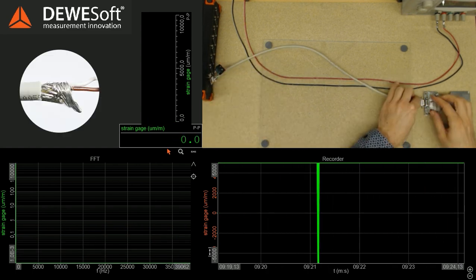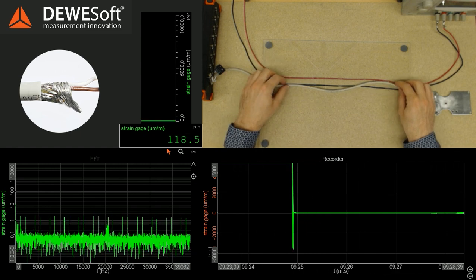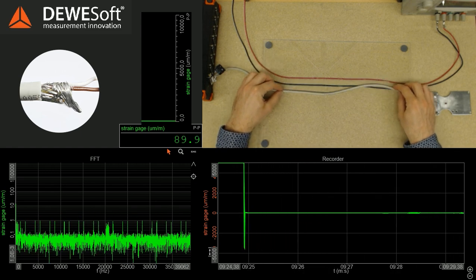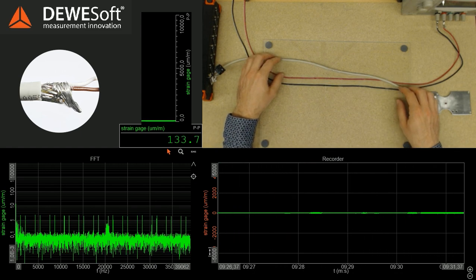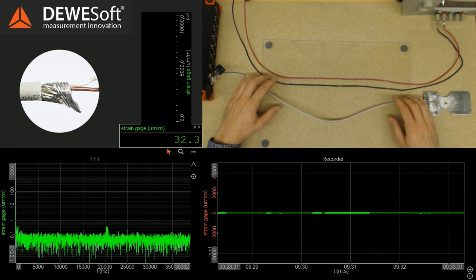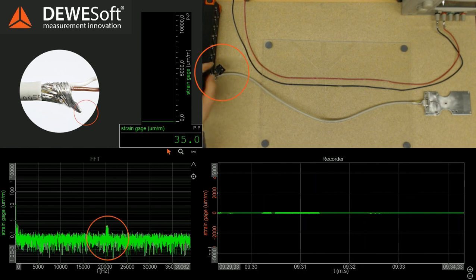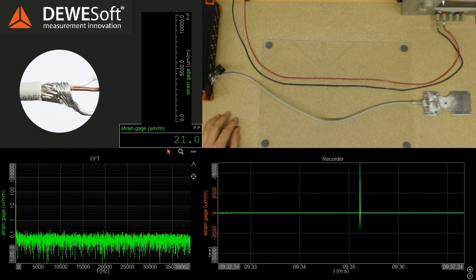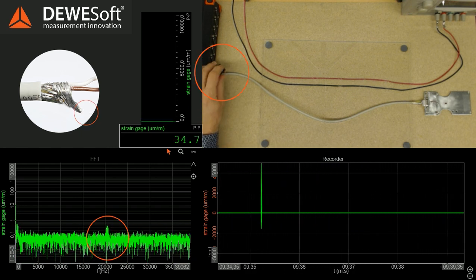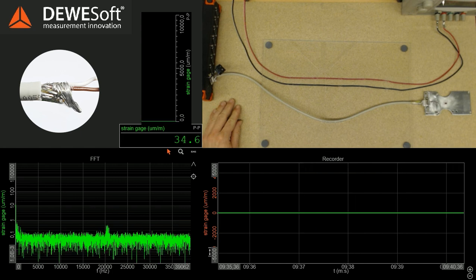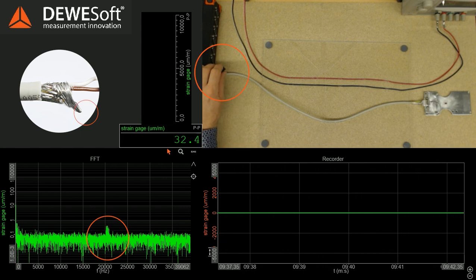Third, we have a twisted shielded cable, but we forgot to connect the shield. Let's connect the shield on the amplifier side. Now even other sources from the environment, like this 20 kHz switching frequency, get muted.